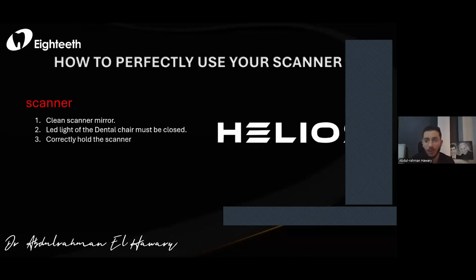And always also make sure that the LED light of the dental chair is closed, because the scanner has a lighting system that is actually projecting a light. If you are directing the LED light of the dental chair over the patient's mouth, then it would disturb the light that is coming out of the scanner, which would in turn disturb the whole scanning procedure. So you need to close the LED light of the dental chair. And also, if you do have a lamp, for example, in your operating room that is directed directly above the dental chair, please try to make it dim as much as possible or close it.